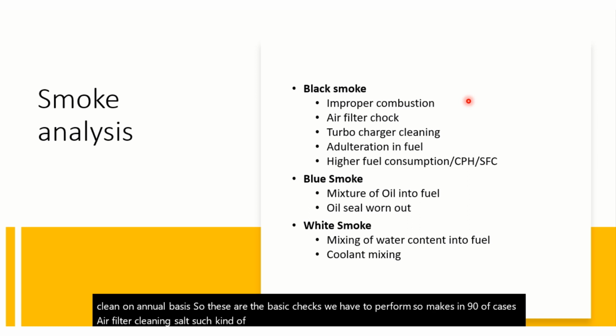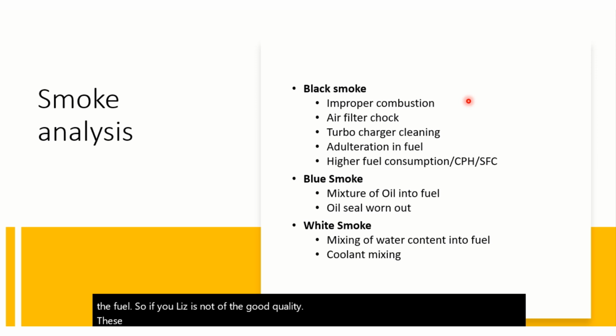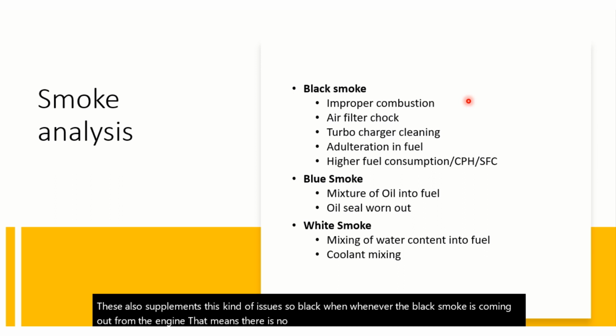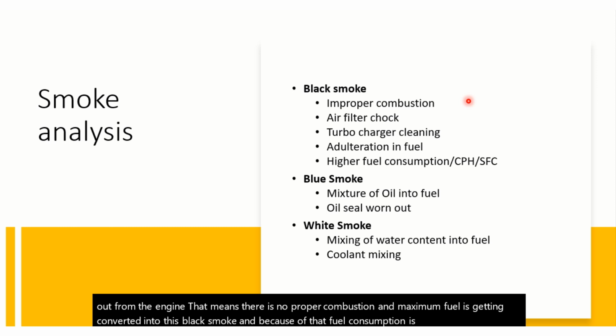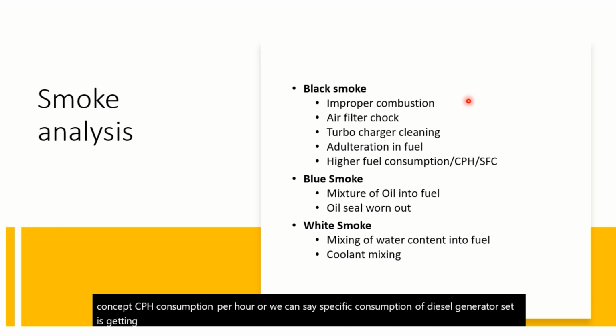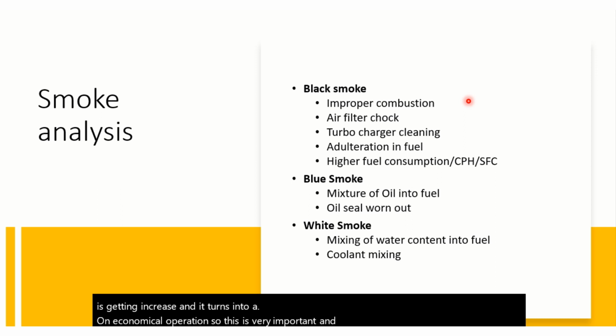Other than that, there is adulteration also in the fuel. So if the fuel is not of good quality, this also supplements this kind of issues. Whenever black smoke is coming out from the engine, that means there is no proper combustion and maximum fuel is getting converted into this black smoke, and because of that fuel consumption is getting increased. CPH, consumption per hour, or we can say specific consumption of the diesel generator set, is getting increased, and it turns into an uneconomical operation. So this is very important, and we have to ensure it by doing corrective maintenance.